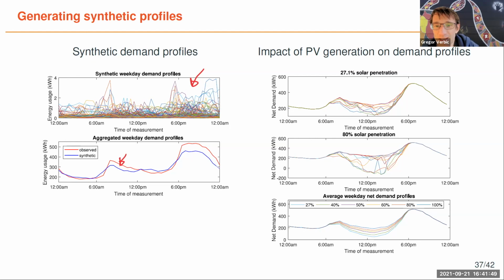On the right, another demonstration of why we need statistical approaches. If you simply use averages, even for 100% penetration of rooftop solar where every house has rooftop solar, you still won't get reverse power flow. Whereas if you use a statistical approach, you can see that in some realizations the total power flow can actually be negative, meaning that particular customer is feeding power into the grid. This is obviously missed if you simply use averages.